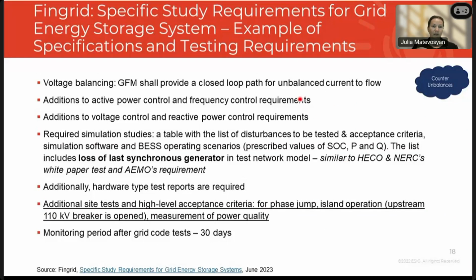So it basically describes how a provision between grid forming functions, and then going into longer term providing frequency response and voltage support, how that operation is expected to be done. And then they have required simulation studies. There is a table that lists disturbances to be tested, acceptance criteria, and simulation software to test it in. That basically points you towards whether a phasor domain simulation or an EMT simulation is required.